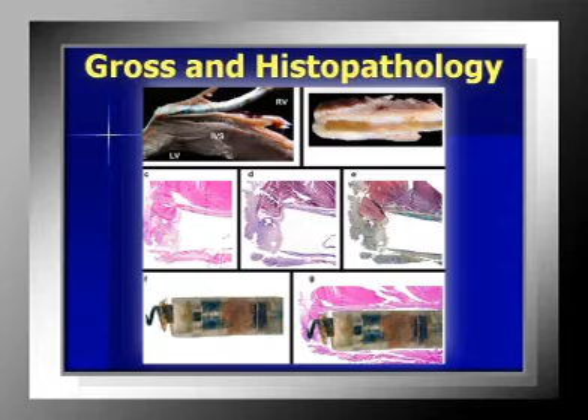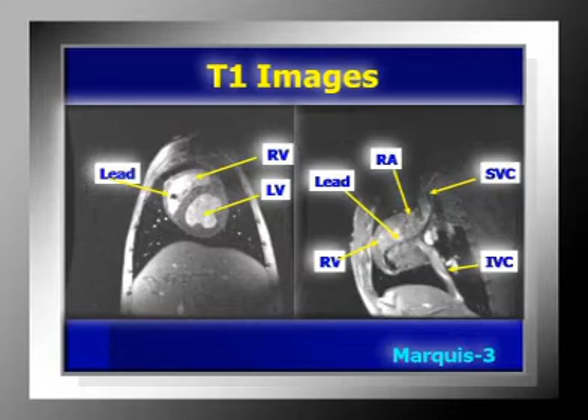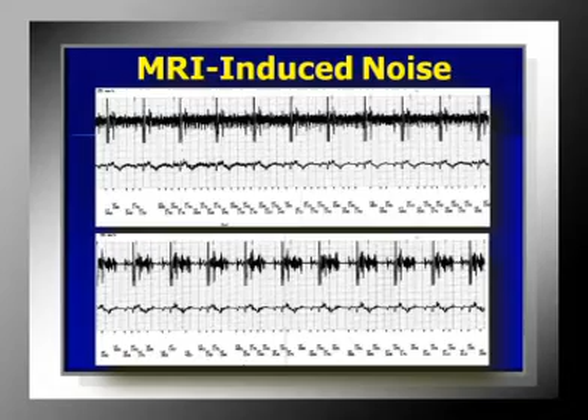And then pathology, the important one is actually shown here where there's Masson's trichrome stain. This is where the lead was. There's very little blue. In the blue, there's a little bit here, there's a little bit here. So there was no evidence of damage to the tissue. And then the images, you can actually see the lead here, you can see the generator here, but you actually see the heart quite nicely. So you can actually get diagnostic quality images. There is some noise in the ECG circuitry of the device, which would be interpreted as ventricular fibrillation. So you have to actually turn the device off, but that's actually not a problem.